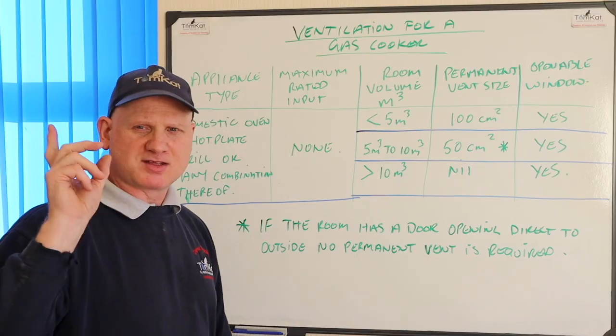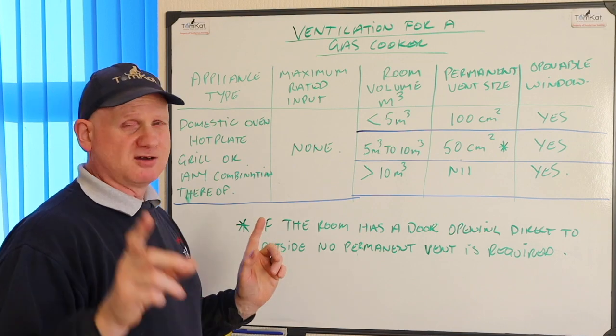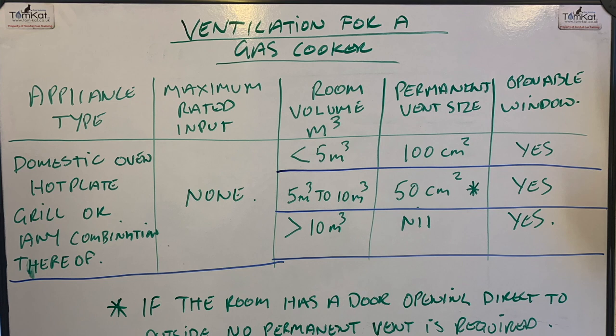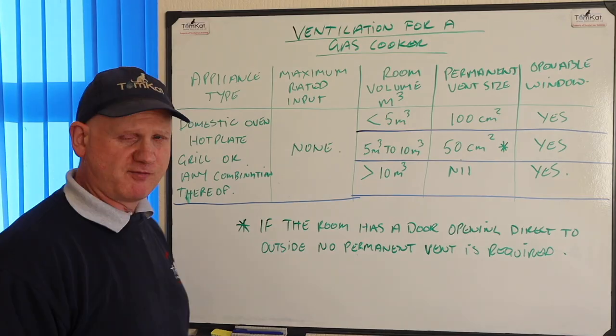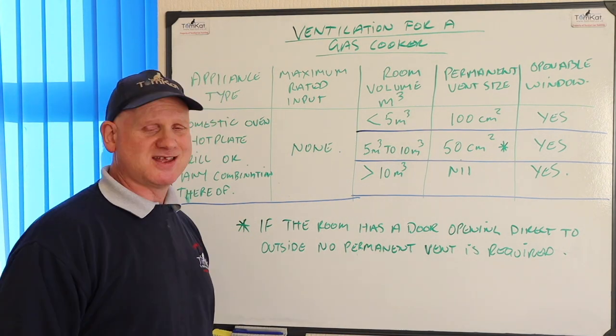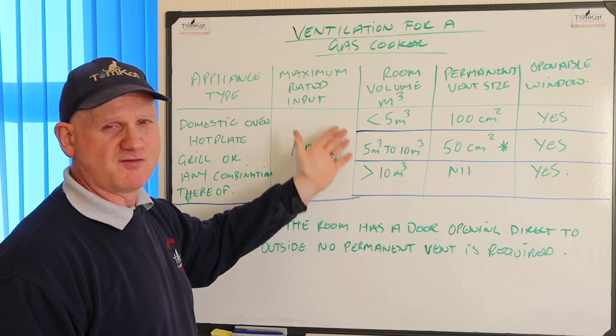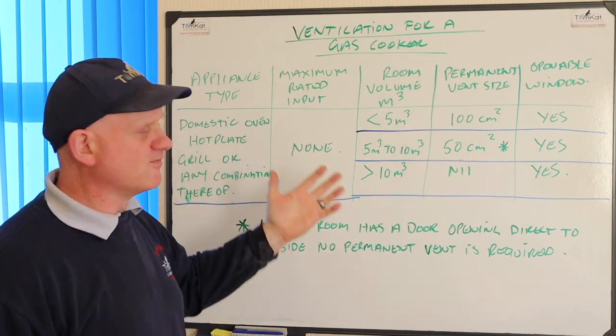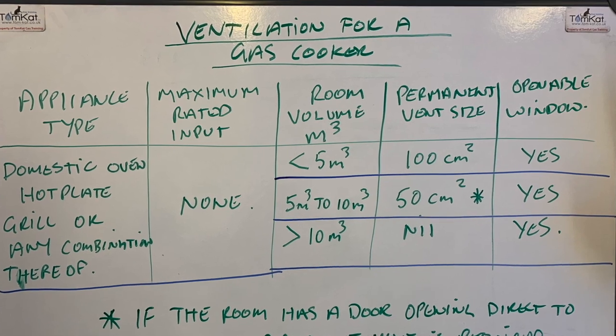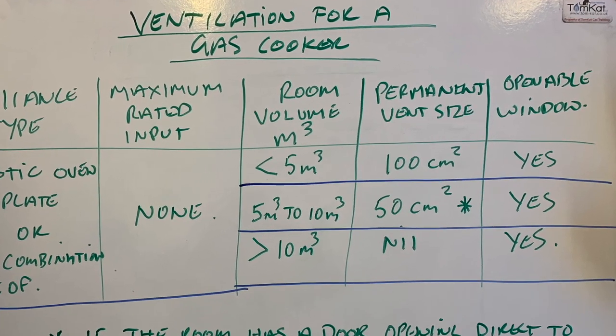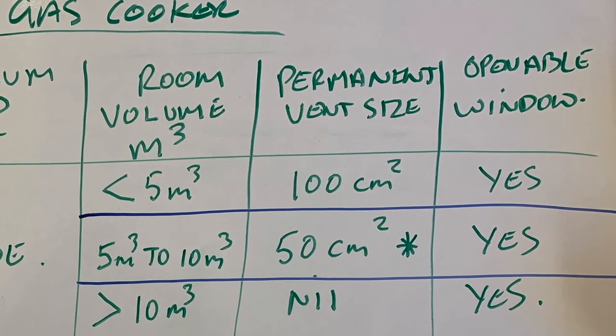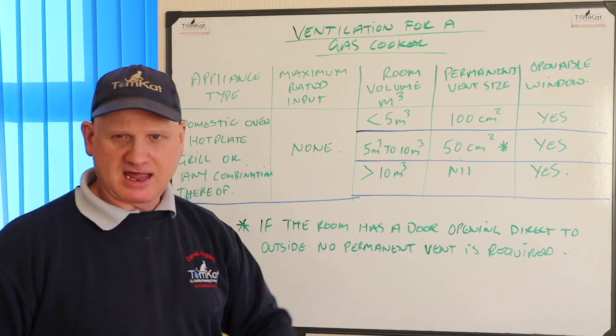Let's have a quick look at the ventilation requirements for cookers. The appliance type covers a domestic oven, hot plate, grill, or any combination thereof. It doesn't matter what the maximum rated input is — you still need to refer to this section about room volume and the size of permanent ventilation required. If we have a room volume of less than five metres cubed, we'll need 100 centimetres squared of free air plus an openable window or any other means of extraction.